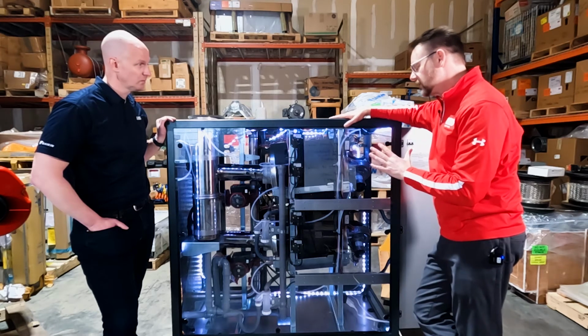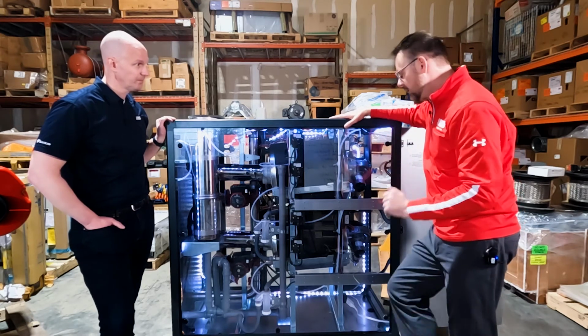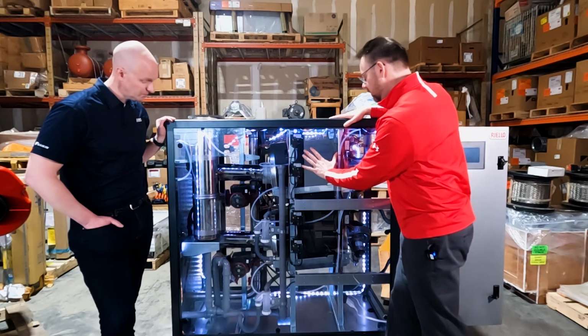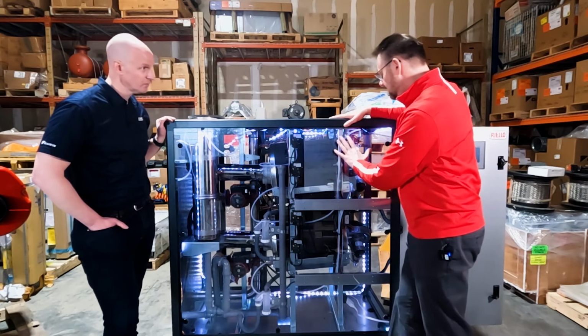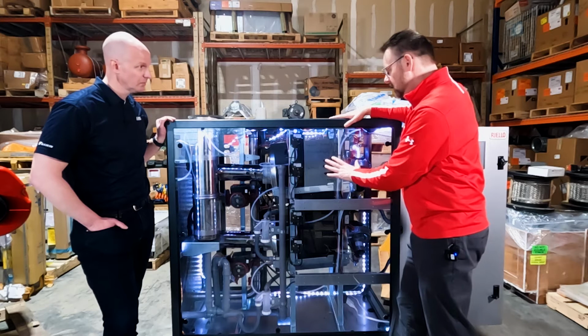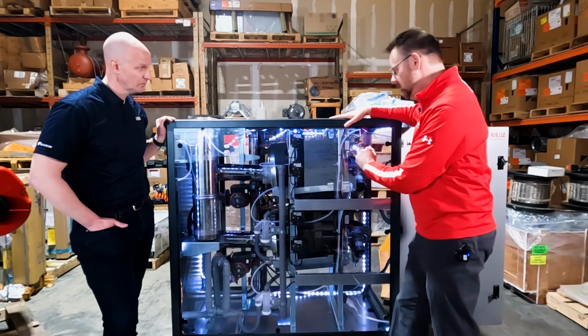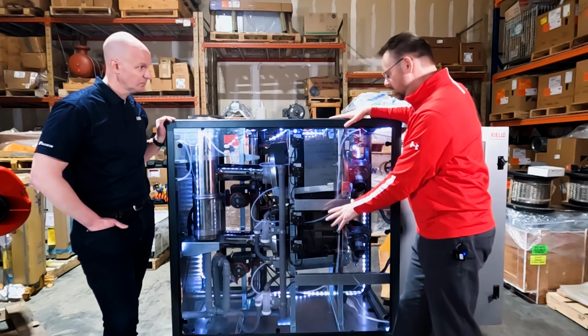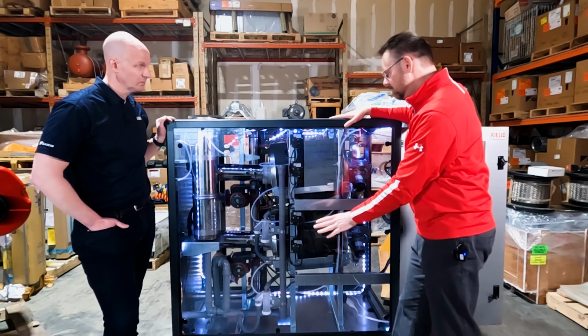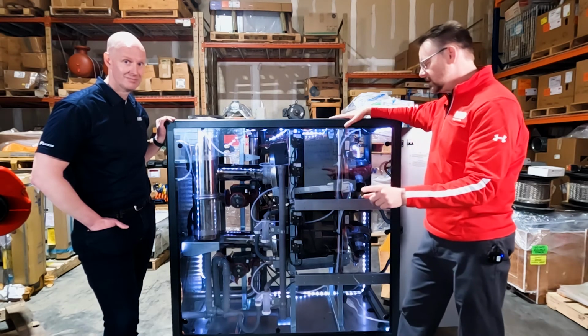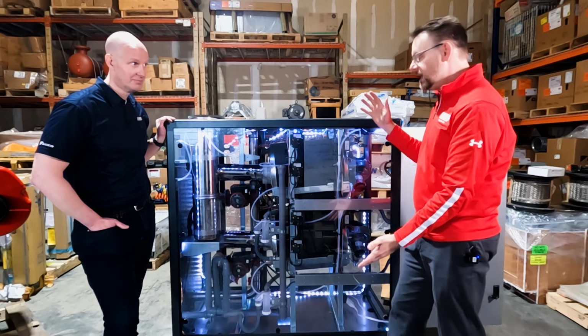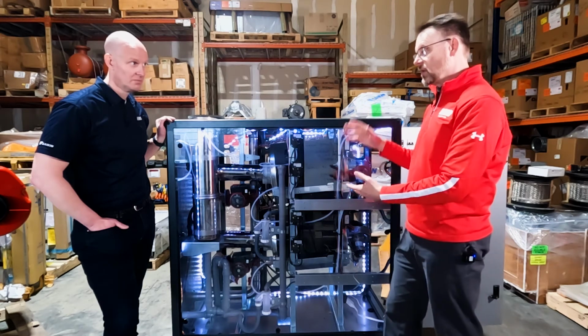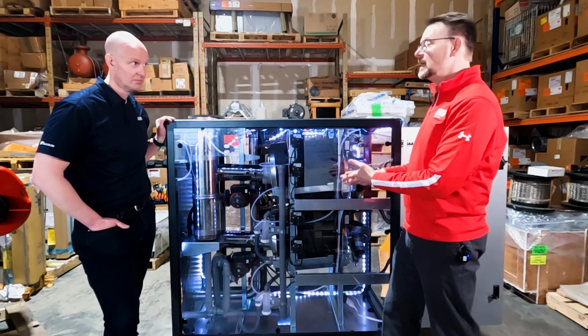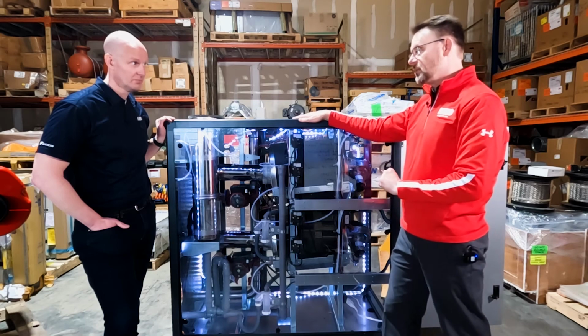And this is where the math gets a little fun. Each of these heat engines at 400,000 BTUs has a 10-to-1 turndown, so the minimum input here is 40,000 BTUs. As you put two of them in the cabinet, we go from 40,000 BTUs, the minimum input of one heat engine, to 800,000 BTUs, the total output of both heat engines. That gives us our range of the installed appliance.